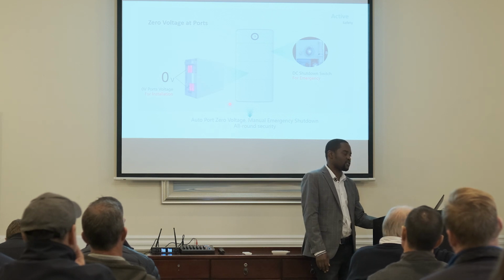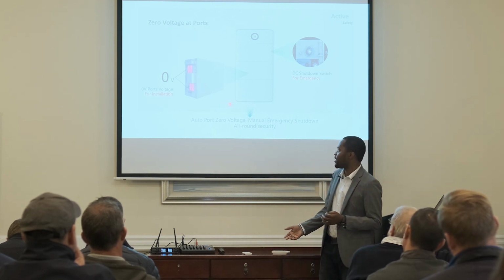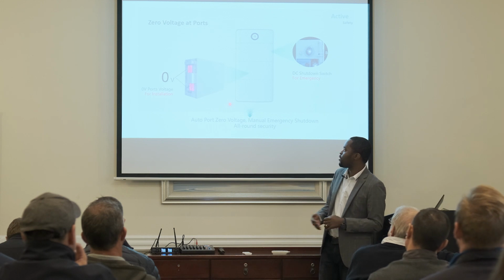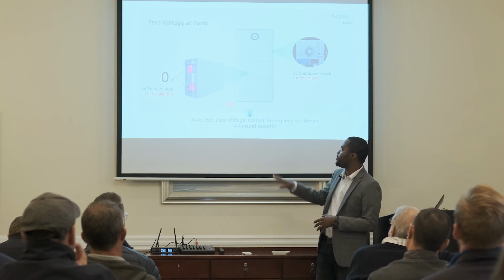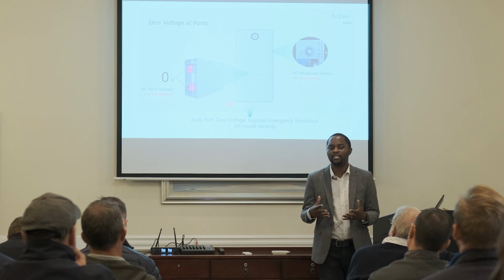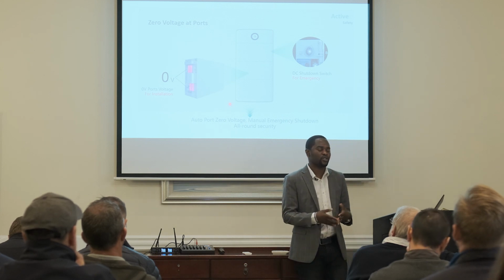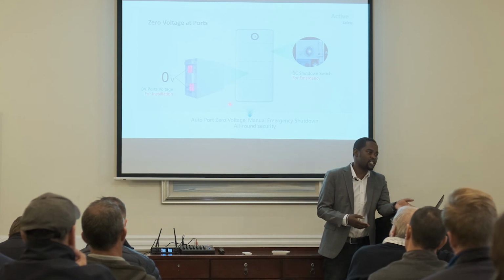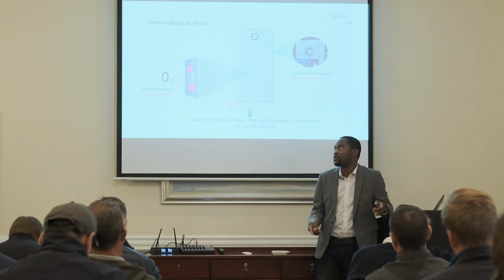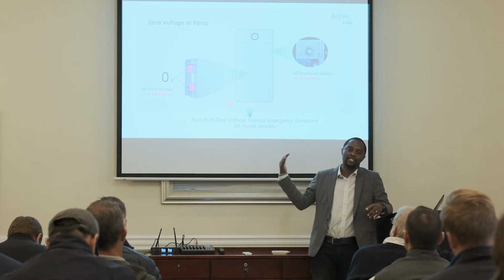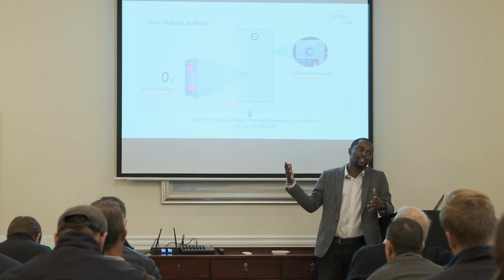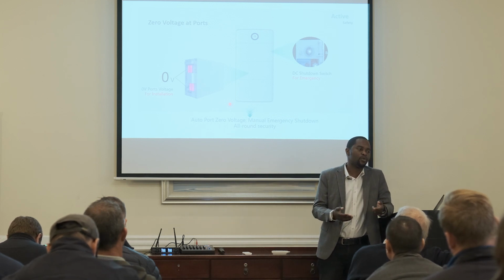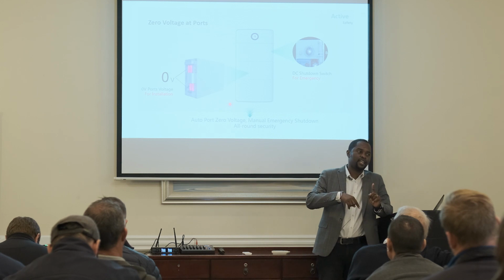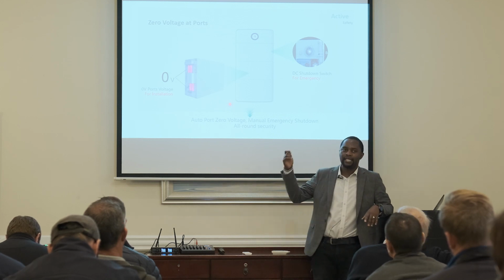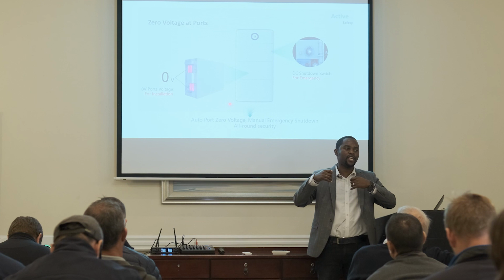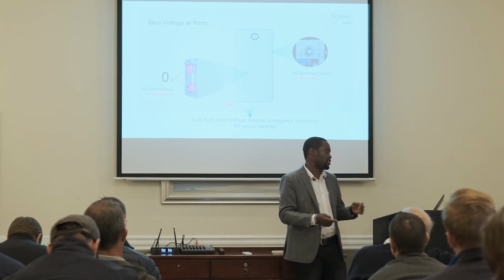If you can see from this, it's a high voltage, from 325 to 400 volts nominal voltage, but if you measure on the voltage terminals, you still get 0 volts. So that is safe, and it's protecting you from accidental contact, touch, or shorting to the ground. If it shorts to the ground, or if you touch the terminals there, you are not at risk at all because it's at 0 volts. It only starts giving that 500 volts when you have connected it and plugged in those MC4 connectors, and it's now safe and the inverter is in operation.